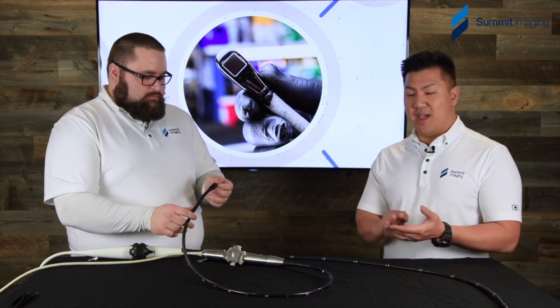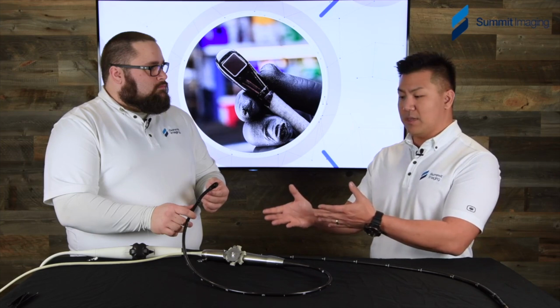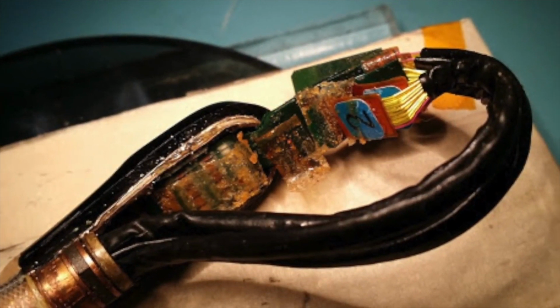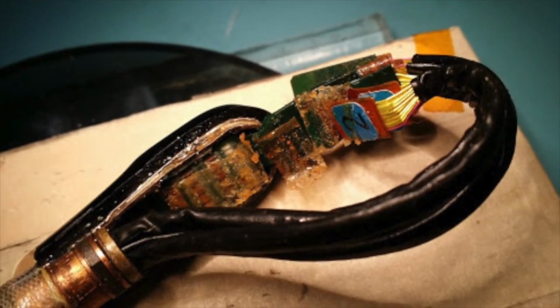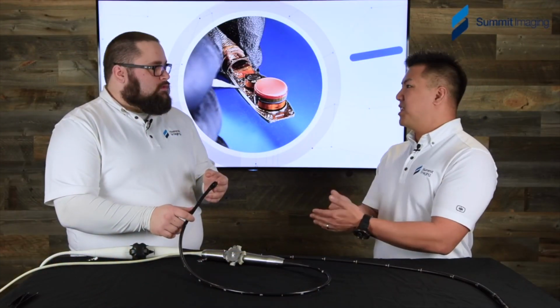Number two, dangerous for the equipment too, because the acid and the fluids and all that stuff that's being used in these caustic environments that these probes go in, it goes into the probe and it actually shorts them out. And if it's not cared for quickly, probe and patient are at risk, but the probe gets the brunt of it because the acid sits on the inside.